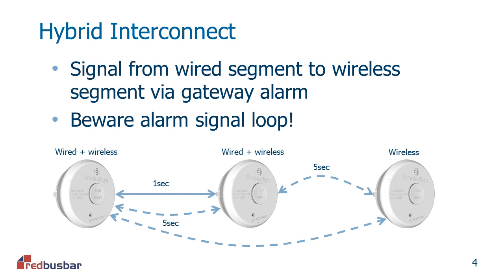Okay, so we've talked about the wired and the wireless smoke alarms. When we need to convey an active alarm from wired alarms on a wired segment to wireless alarms on a wireless segment, we need a gateway alarm, and the gateway alarm incorporates both a wired and a wireless interconnection. The only challenge with the gateway alarm is where there's more than one gateway alarm on the network. So if we look at the network arrangement at the bottom there, imagine an alarm becomes active on the wired and wireless alarm on the left-hand side. Well, across the wired network, that active alarm would be reported to the adjacent wired and wireless interconnected alarm within 1 second. So that'd be a pretty quick response.